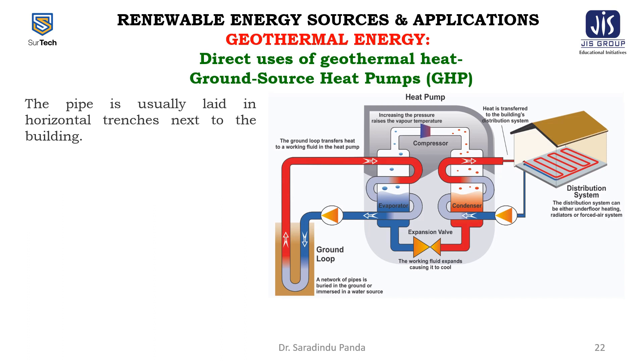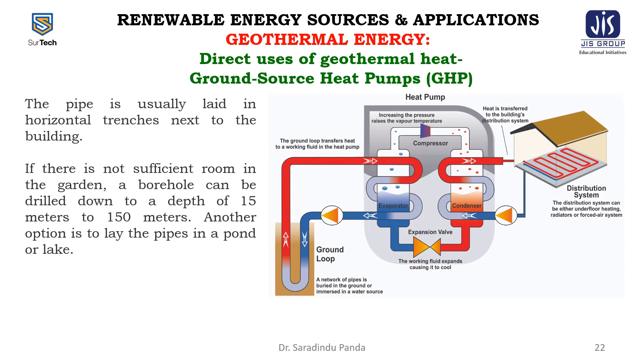The pipe is usually laid in horizontal trenches next to the building. If there is insufficient room, a borehole can be drilled to a depth of 15 to 150 meters, or the pipes can be laid in a pond or lake. The ground loop transfers heat to the working fluid in the heat pump — the evaporator side, condenser side, expansion valve, and compressor. Increasing the pressure raises the vapor temperature via the compressor, and the heat is transferred to the building's distribution system.